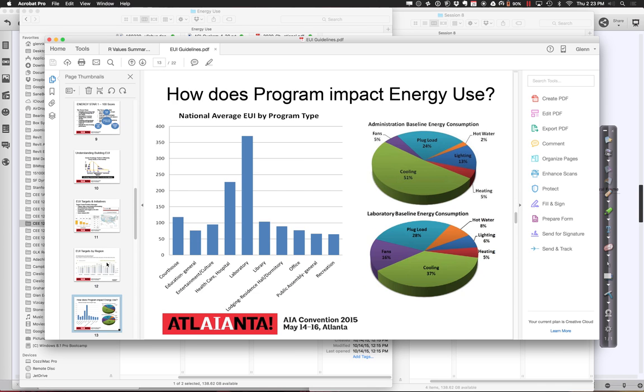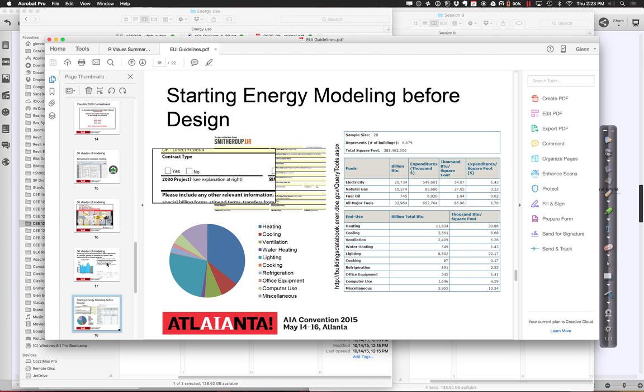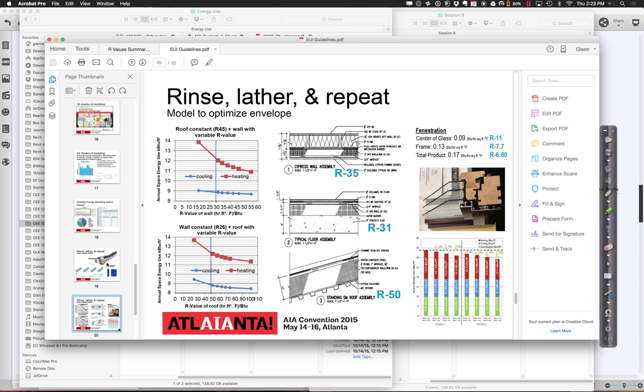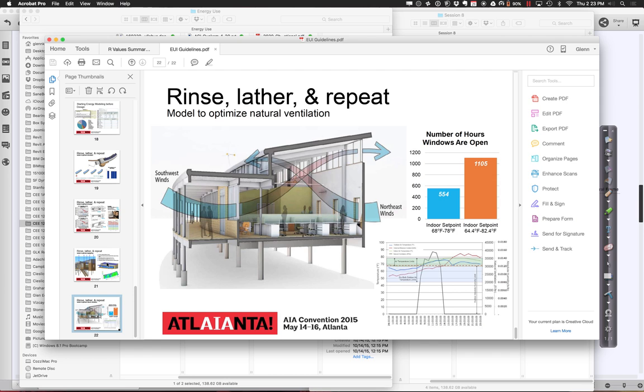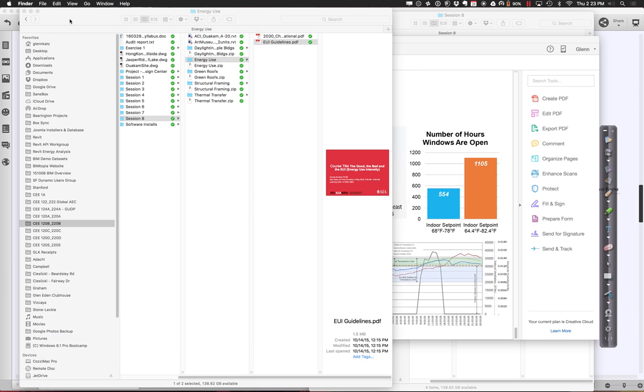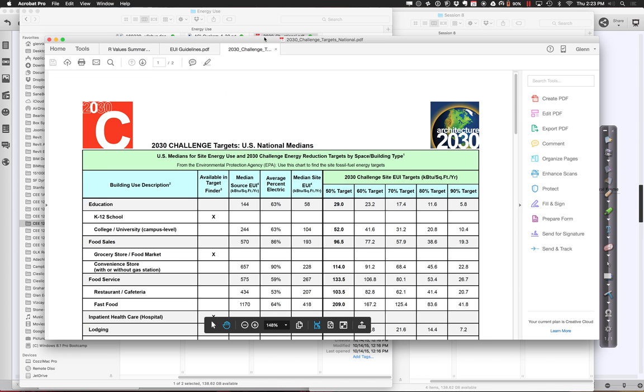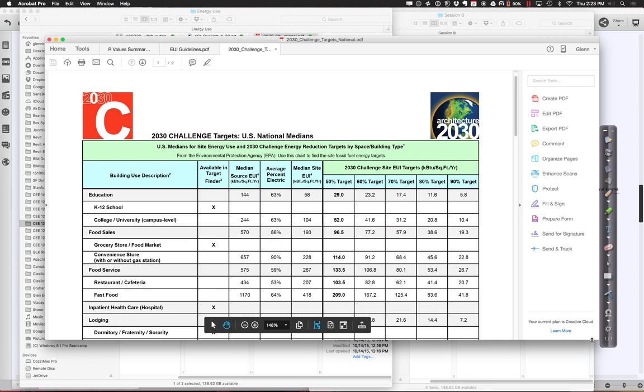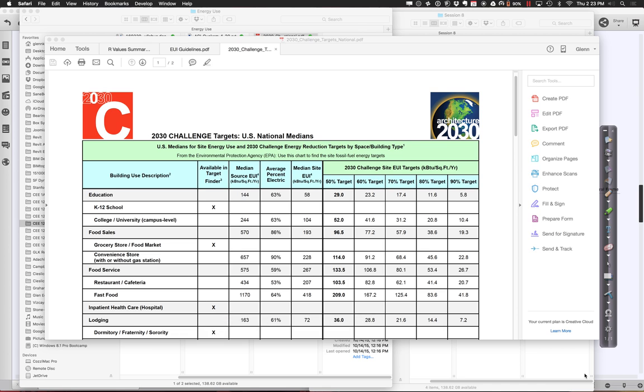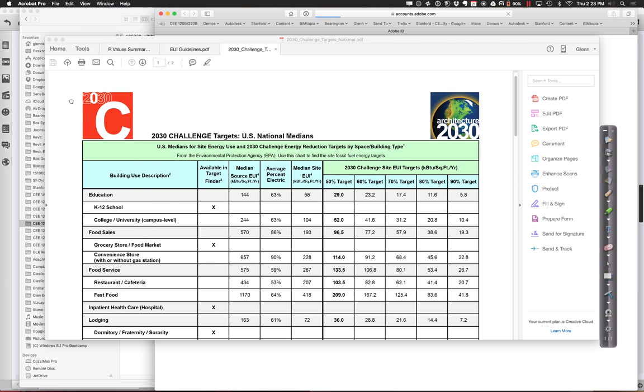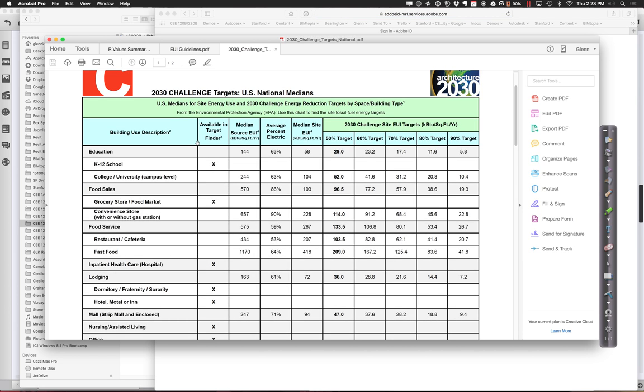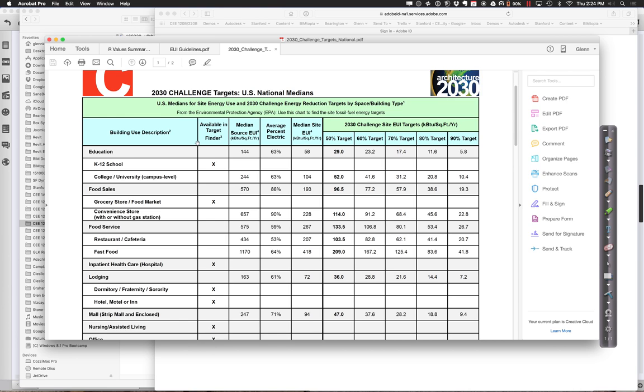The point of this whole paper is really just watch out for the targets. The big message is that there's no simple target for which you should come up with. It's all sort of comparative. This is the 2030 challenge. The idea was that as we move towards the year 2030, we should continually be trying to drop our energies to the point where we're getting closer to a target percentage. For a college or university campus, the 50% target would be that we would use 52 as our EUI. But as we move further towards 2030 and get closer to 100%, we're going to try and get that down to 10.